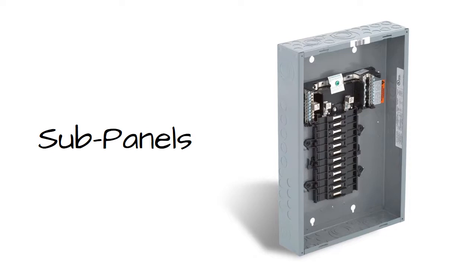We also have to be careful in a sub-panel to isolate the nulls from ground. If the neutral is connected to the ground wire in a sub-panel, then current flows back on both the neutral and on the ground wire. With faulty wiring, it's also possible to have a live panel box, in which case you might be a path to ground. Why mention sub-panels if few have ever even heard of one? Sub-panels offer an advantage which I will discuss much later in another video.